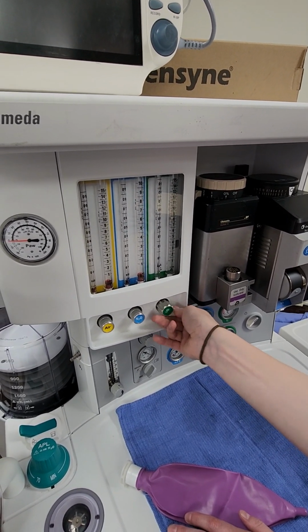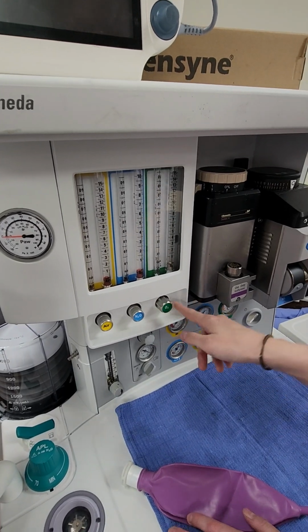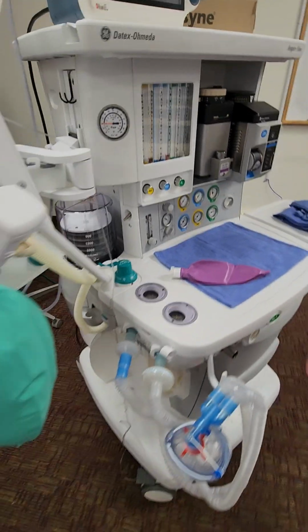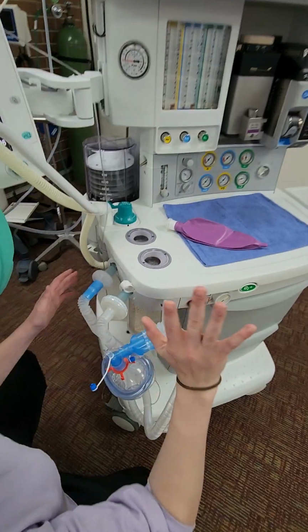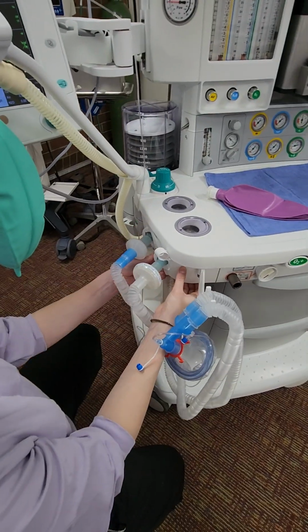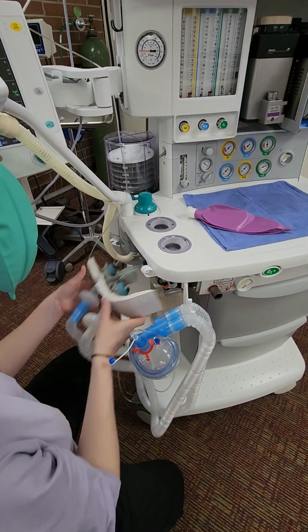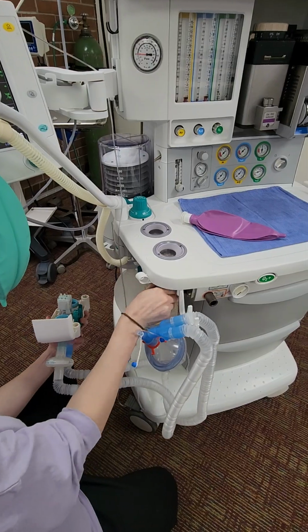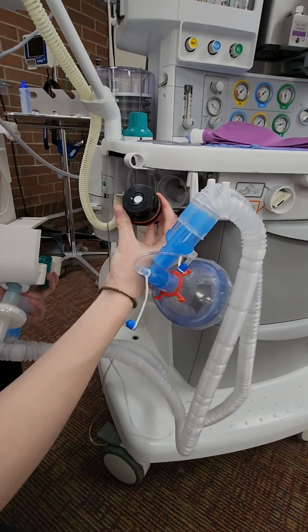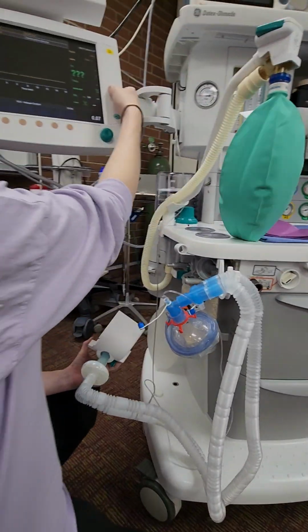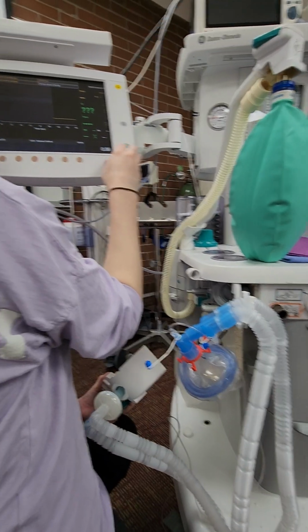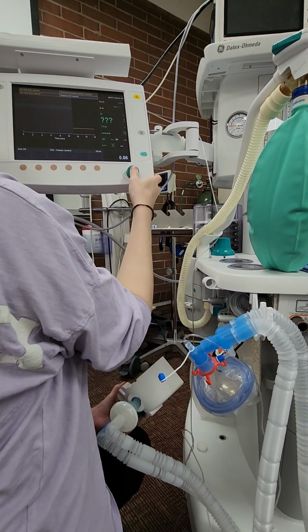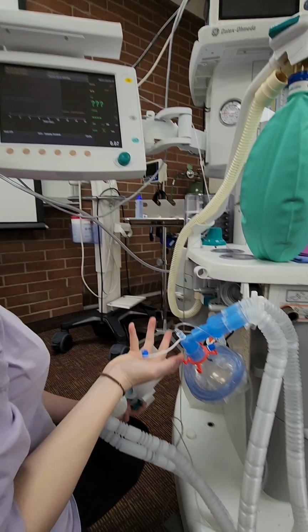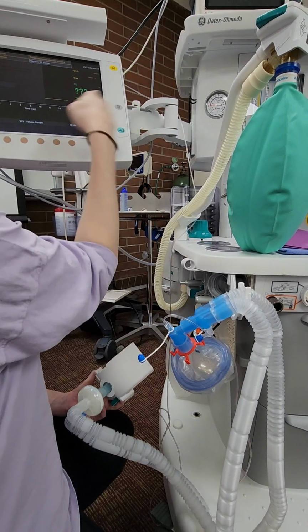Sounds good, looks good. It's not sticking. Close it. So now you can check your SpO2 monitor. Actually, your oxygen analyzer. Take this disc out. This is the oxygen analyzer you want open to air. You'll go on this machine. You'll go to set up calibration, O2 sensor calibration, 21% since it's open to air. And then it'll run through that test.